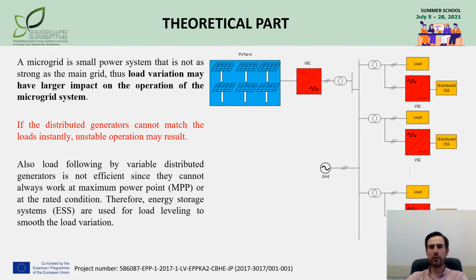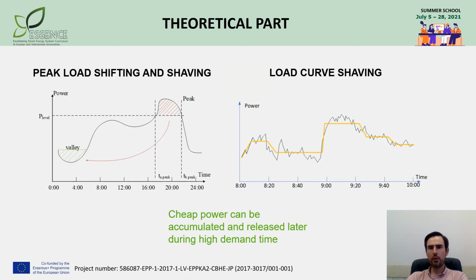For example, when the load changes rapidly, it's necessary for the distributed generators to adjust the output with larger speed. They shall have, in other words, a higher ramp rate. If generators cannot match the loads promptly, this may result in instabilities of system variables, like voltage and frequency collapses. This problem is especially urgent for variable resources since the maximum output depends on the availability of primary resources like sun, wind, and so on. Thus, to maintain stable operation of systems with a large share of such generation, energy storage systems are required. Energy storage's main job includes peak load shifting and shaving.